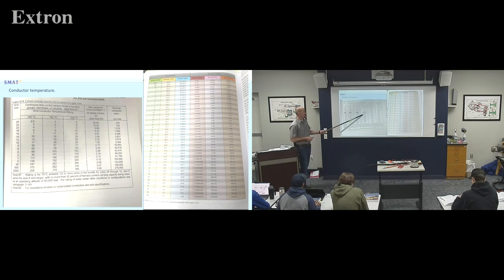But basically, the way to kind of be thinking about that is the insulation on the wire is rated to be able to withstand that kind of temperature before it melts, it breaks down, it starts letting voltage through. And if I let my wire get to be 200 degrees, it's going to reject the heat a lot faster than a wire that's only 100 degrees, right? So if we're okay with the wire getting hot, we're saying, okay, it'll be able to reject the extra heat that's built up from our extra amperage. So that's essentially what they're saying in this simplified chart that they give us here.